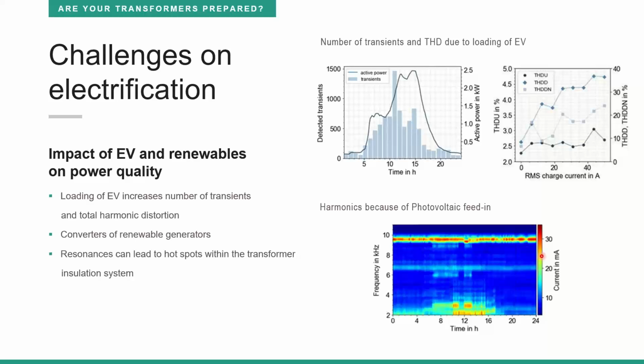But also electric vehicles and renewables have a strong impact on the power quality. We can see in the upper graphs the number of transients and the total harmonic distortion due to loading of electric vehicles. And we can see that during the day, when we have a high loading demand, also a lot of transients occur, transient overvoltage occur in the network. Also, total harmonic distortion is increased by the loading current.